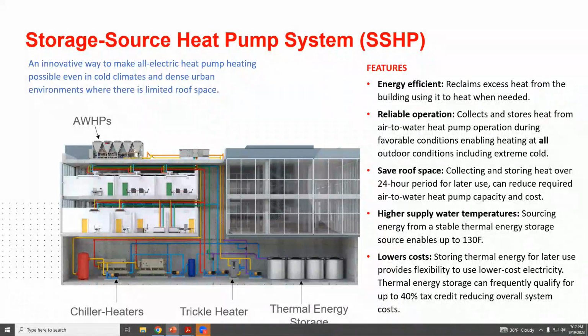Reliable operation, because we aren't reliant on ambient conditions—as long as we have water to pull heat out of and build ice, we have a reliable source of heat. As long as we can put that out into a loop within the building, our water to water products will be able to build heat. All of that comes into sizing of a system, but it's a good way to have reliable heat throughout. It also saves roof space, which we already talked about—it's a good way to reduce the amount of air source heating needed on your roof.